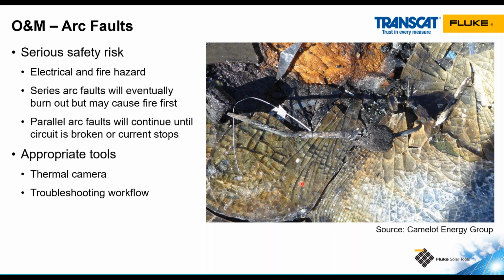In this picture here, this was a module interconnection where the positive and negative side were not fully mated together. So that was a high resistance series arc fault that eventually heated up and caused the connector to burn out. You can see a little bit of the remains of the plastic components. That ended up causing a roof fire on this system. So that was a catastrophic failure due to an arc fault.